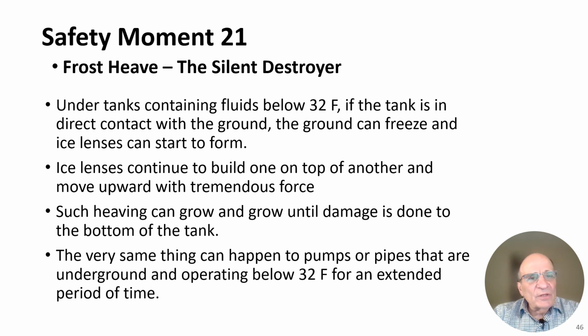The moment number 21, frost heave. I call it the silent destroyer. Under tanks containing fluids that are below 32 degrees Fahrenheit, if the tank is in contact with the ground, the ground can freeze and ice lenses can form. Ice lenses continue to grow, building one on top of the other, and move upward with tremendous force. They can lift buildings, they can lift tanks, and they can lift them unevenly because they may form in one place and not in another, and that can cause a tank leak.